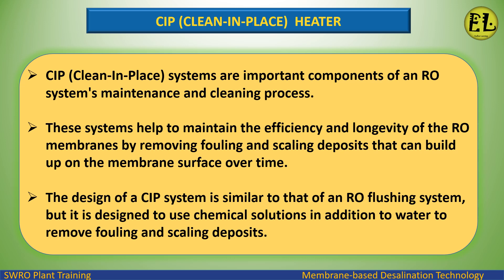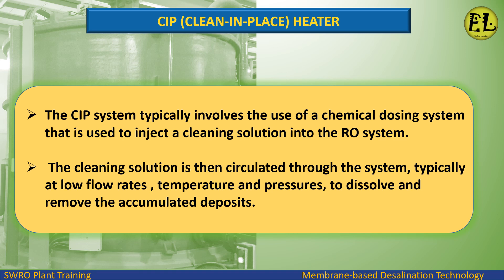CIP Clean-In-Place systems are important components of an RO system's maintenance and cleaning process. These systems help to maintain the efficiency and longevity of the RO membranes by removing fouling and scaling deposits that build up on the membrane surface over time. The CIP system uses chemical solutions in addition to water, typically circulated at low flow rates, temperatures, and pressures to dissolve and remove accumulated deposits.